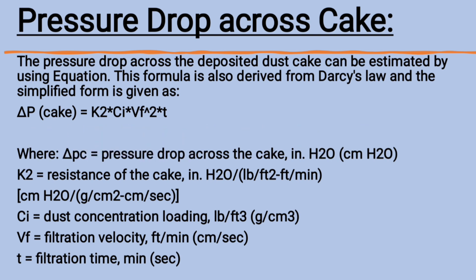Next, we understand the pressure drop or delta P across the dust cake. The pressure drop across the deposited dust cake can be estimated using an equation also derived from Darcy's law. The simplified form is: delta P_C = K2 × CI × VF² × T, where delta P_C is the pressure drop across the cake, K2 is the resistance of the cake, CI is dust concentration loading, VF is filtration velocity, and T is filtration time.